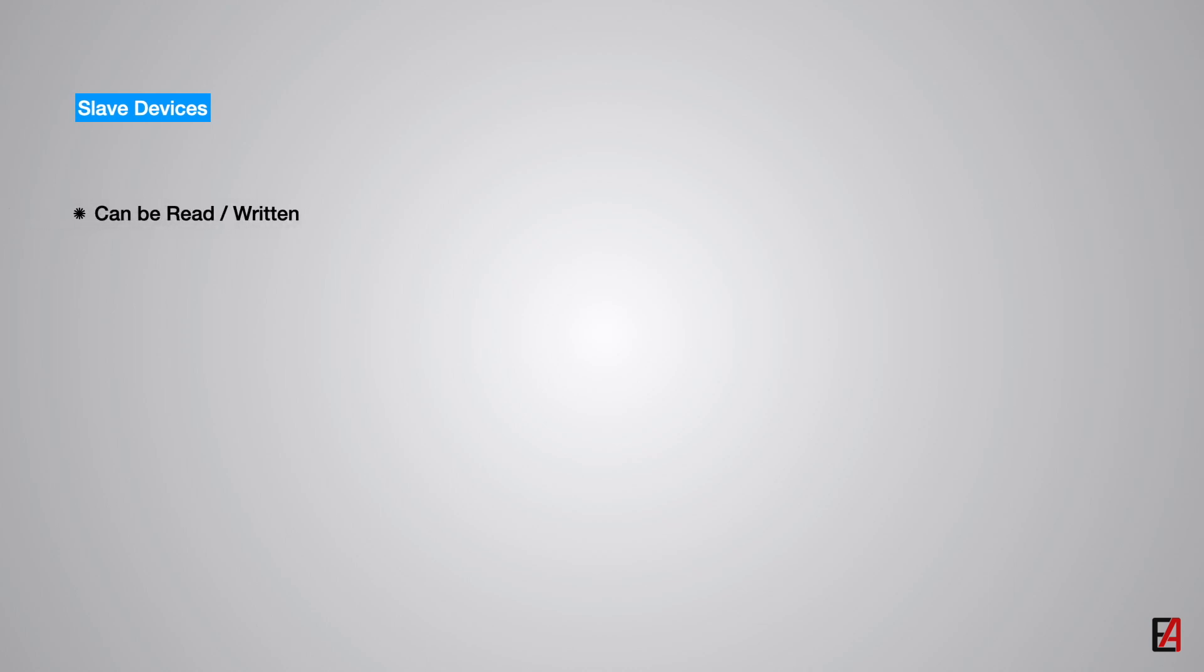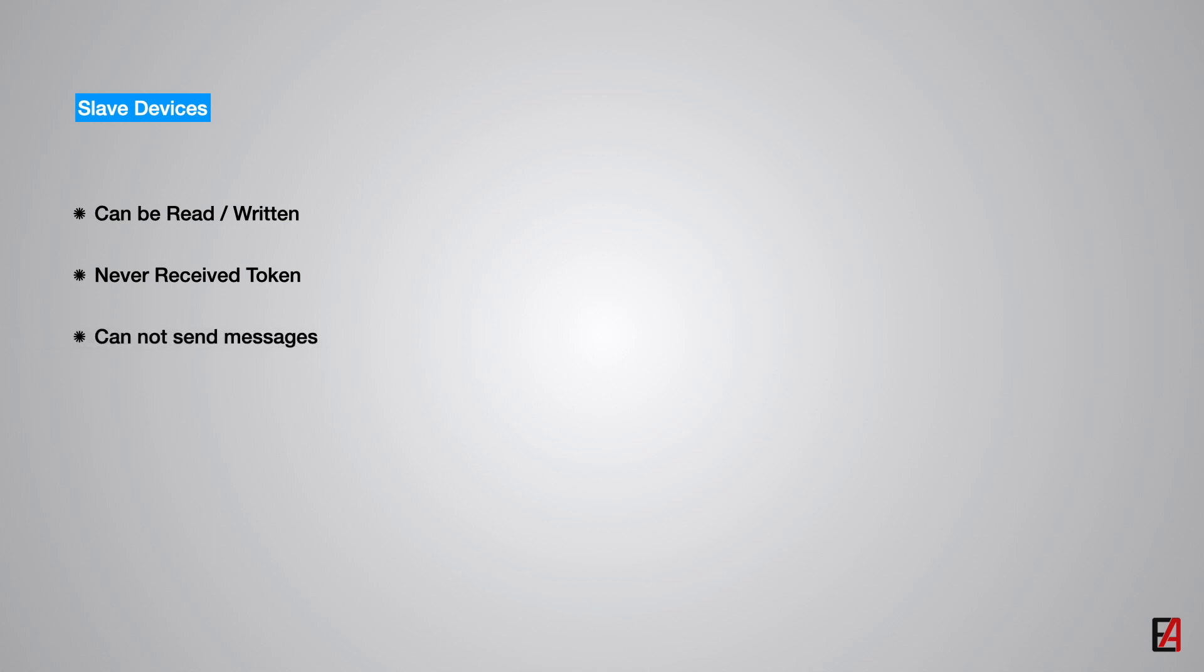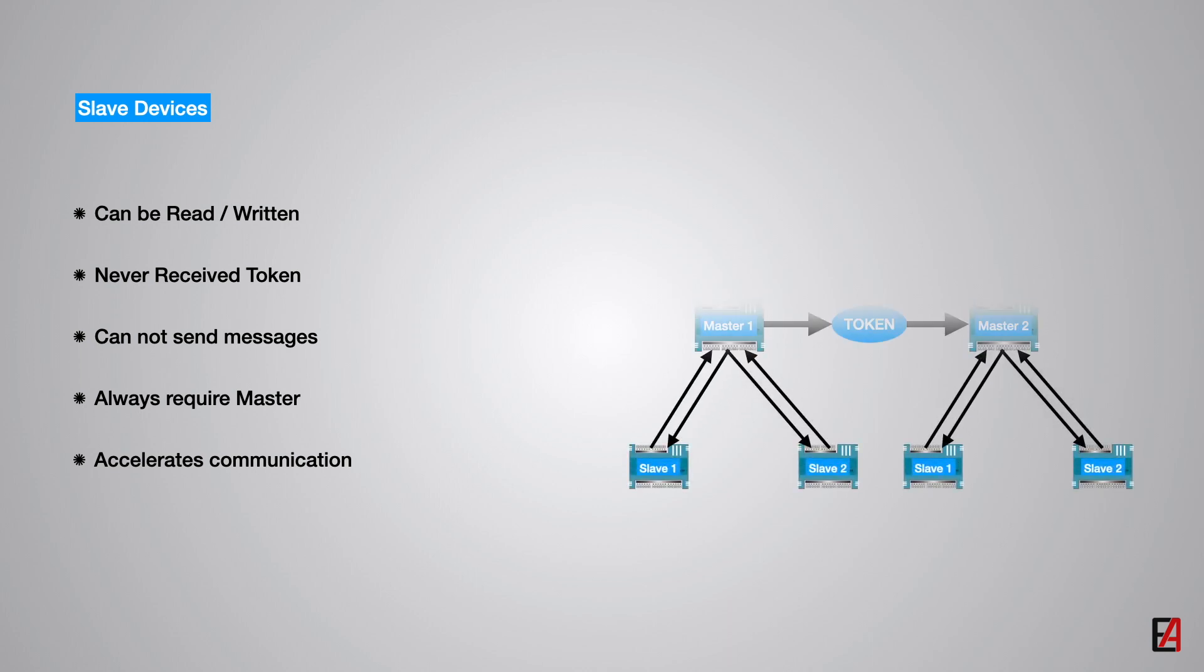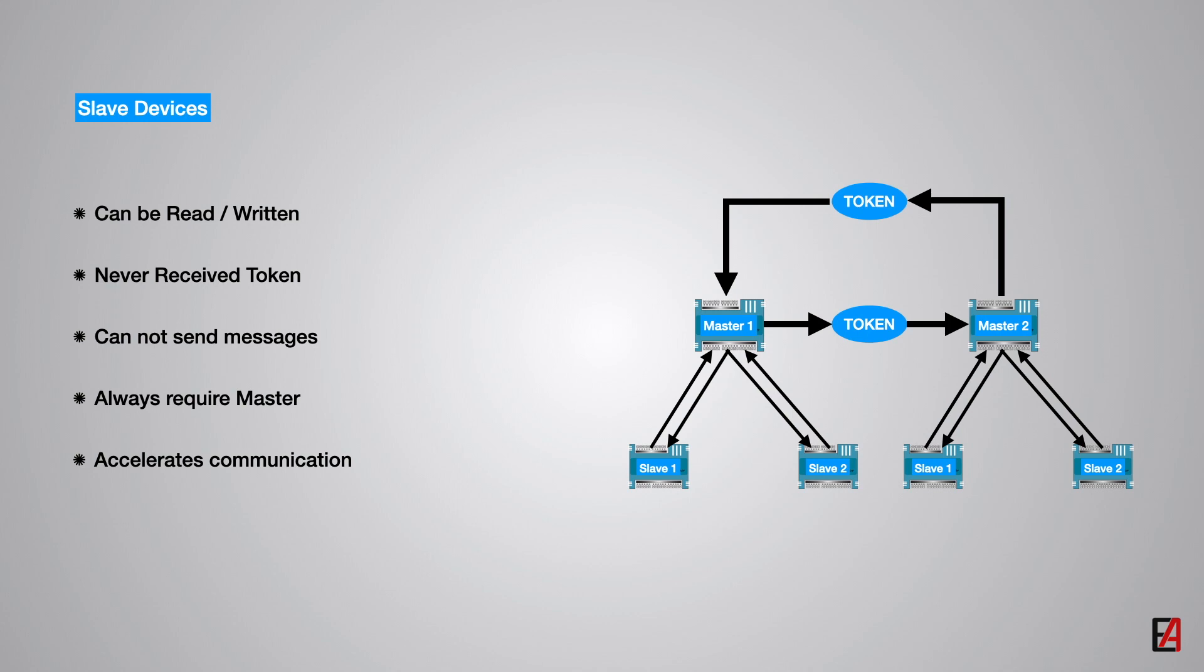Slave devices can be read or written but never receive the token. The disadvantage of slave devices is that they cannot send messages and always require a master on the network to establish communication. On the other hand, it has the advantage of transferring less tokens on the EIA-485 bus which accelerates overall communication. However, the disadvantages outweigh the advantages so that most MSTP devices are set as master devices.